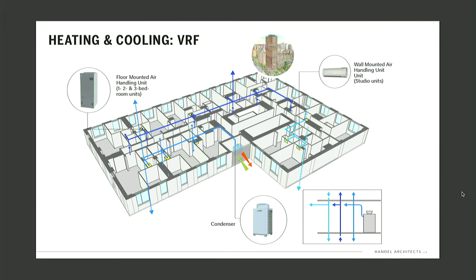This is Sendero Verde. Now, the orientation is on the New York grid, which is not north and south. So north is up on the page, and we ended up making 3 zones. We have this eastern zone, a southwestern zone, and then this north zone here. And so the loop here is now, instead of being 2 floors, it's 3. And you'll see in the masonry building, we decided we wanted to take the refrigerant loops inside. So it's an interior route. It only crosses the corridor a couple times. That's where you need to be 2-hour rated.